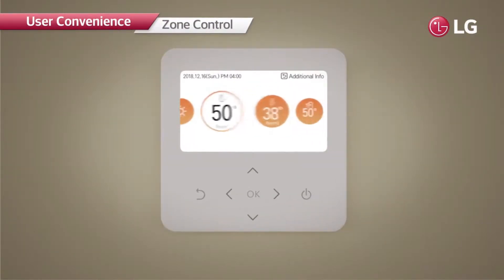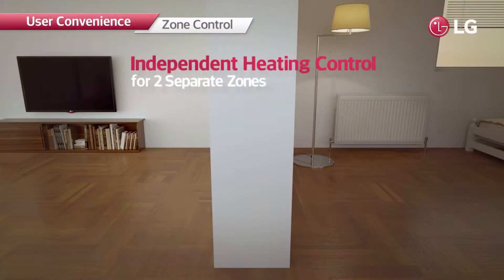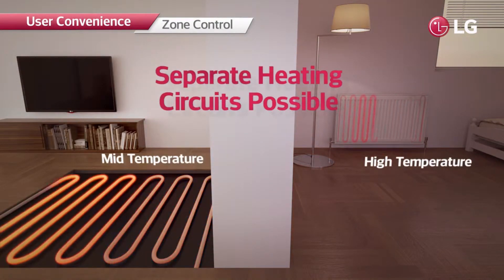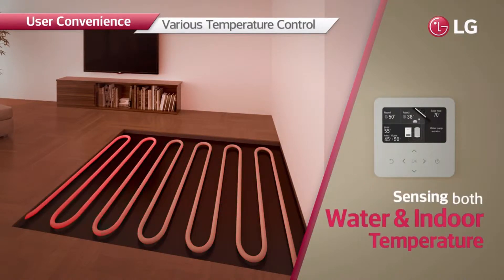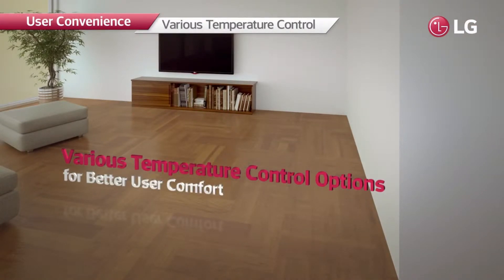The system is also capable of controlling heating operation in a smart way for each individual space. Every space can be set to suitable temperatures rather than setting the entire floor with a single temperature. As R32 Monoblock senses both the indoor temperature and leaving water temperature, it can reduce leaving water temperature when indoor temperature rises, thereby ensuring users a comfortable environment.